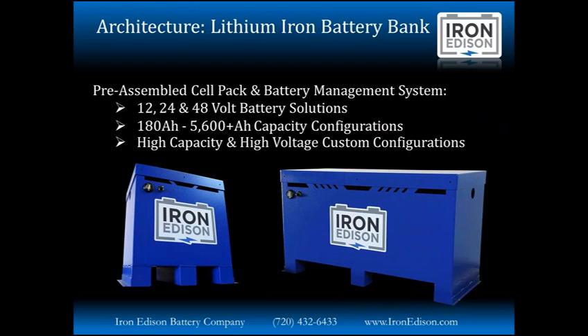The architecture of a lithium-ion battery bank from Iron Edison is a pre-assembled cell pack and the battery management system, completely enclosed in a blue enclosure like you see here. They are available in 12 volt, 24 volt, and 48 volt solutions. Amp hour capacities range from 180 amp hours up to over 5,600 amp hour configurations. And again, we can do high capacity and high voltage custom configurations. So if you have any unique challenges or special projects, these are the type of projects we really thrive on. So give us a ring or reach out to us however you can. Tell us the details and the requirements of the project, and there's a very good chance we can come up with a perfect solution for you.